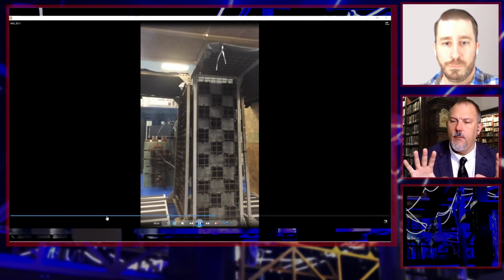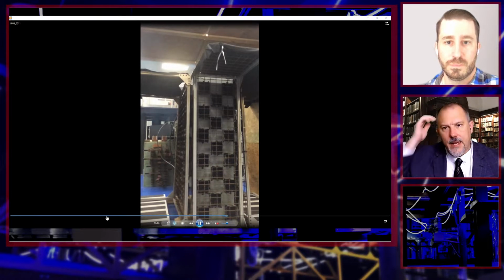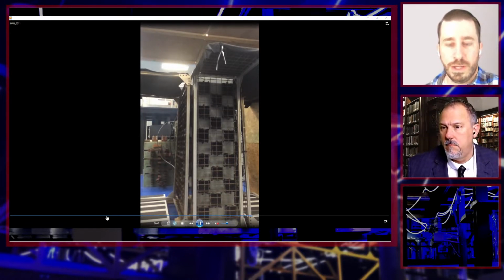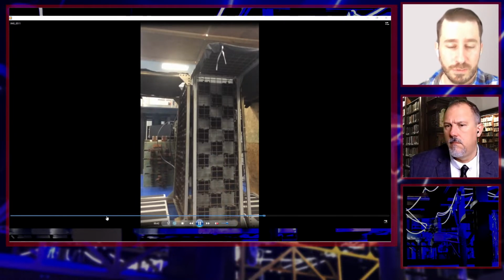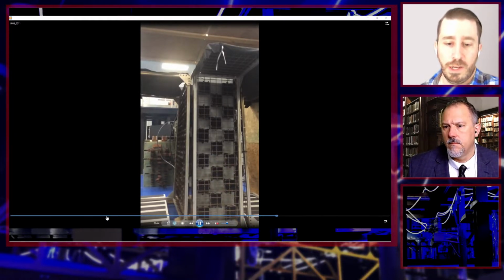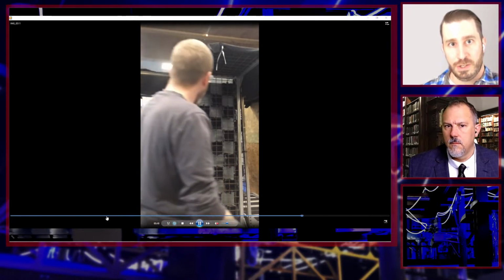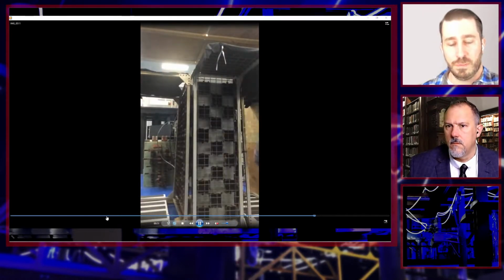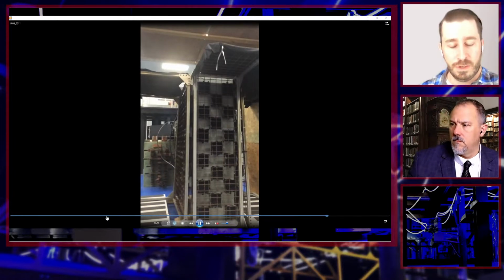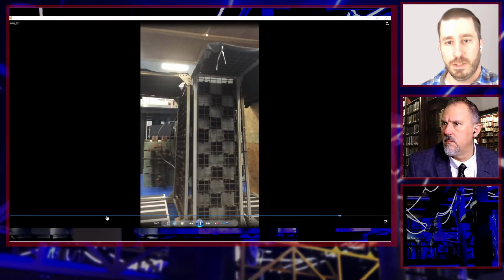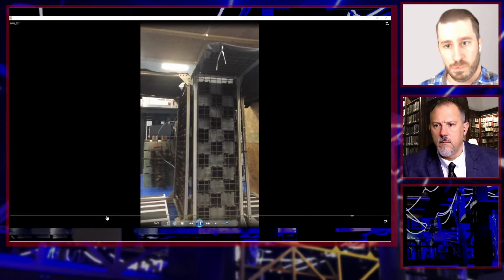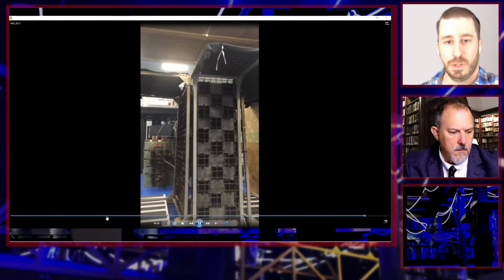The rack that we have in front and on the sides — is that measuring temperature, what is that? So that's part of the criterion for arc resistant equipment. As we talked about around the initiation, you've got different pieces of equipment and different areas of the compartments that you've got to identify and assume as the worst case.